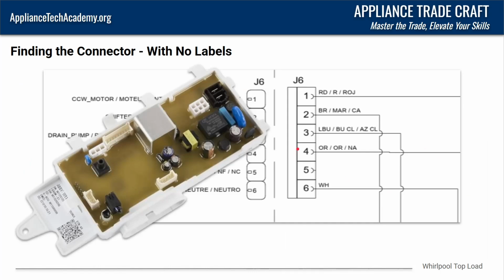So one other thing to say on these units is we've got this filler stuff here. It's there to prevent moisture from getting on the board and causing it to do anything. Now the issue is, we're looking for the J6 connector, but there's no pinouts. You don't see any callouts here. This is where it's just a simple process of elimination. You're just using deductive reasoning to determine which connector this is.